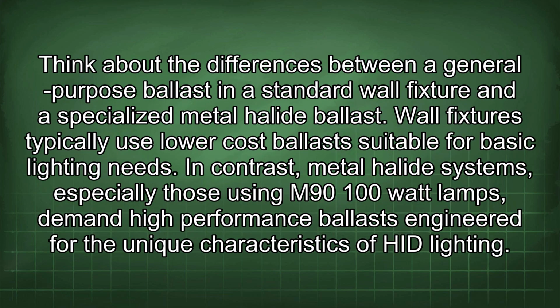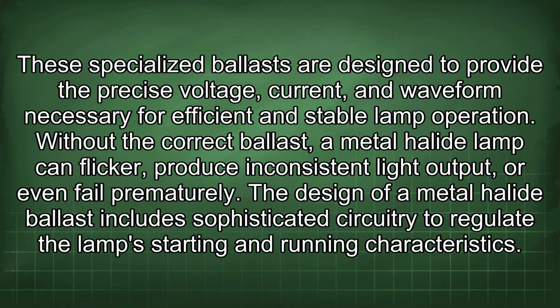Think about the differences between a general-purpose ballast in a standard wall fixture and a specialized metal halide ballast. Wall fixtures typically use lower-cost ballasts suitable for basic lighting needs. In contrast, metal halide systems, especially those using M90 100-watt lamps, demand high-performance ballasts engineered for the unique characteristics of HID lighting. These specialized ballasts are designed to provide the precise voltage, current, and waveform necessary for efficient and stable lamp operation. Without the correct ballast, a metal halide lamp can flicker, produce inconsistent light output, or even fail prematurely.